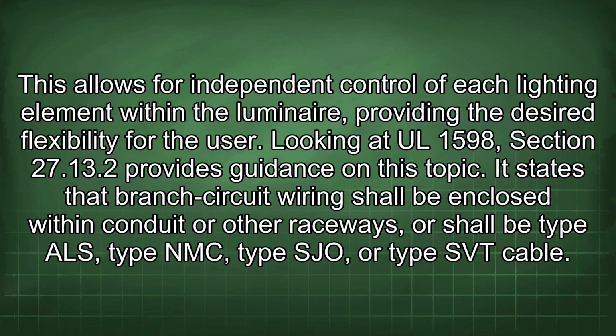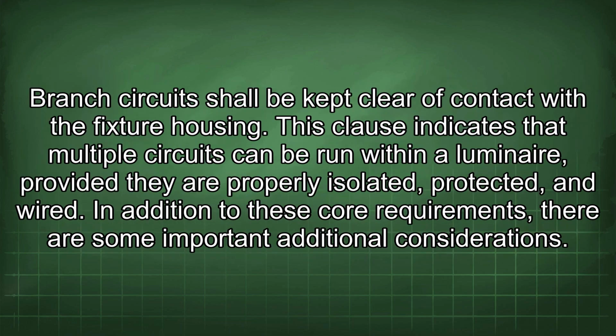Looking at UL 1598, Section 27.13.2 provides guidance on this topic. It states that branch circuit wiring shall be enclosed within conduit or other raceways, or shall be type ALS, type NMC, type SJO, or type SVT cable. Branch circuit wiring shall be kept clear of contact with the fixture housing. This clause indicates that multiple circuits can be run within a luminaire, provided they are properly isolated, protected, and wired.